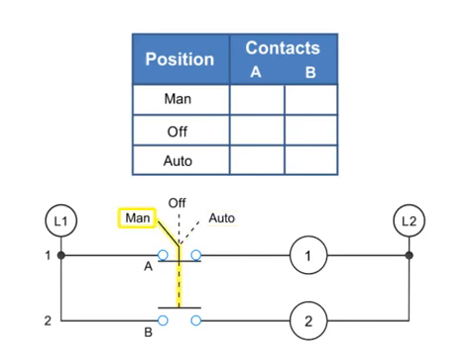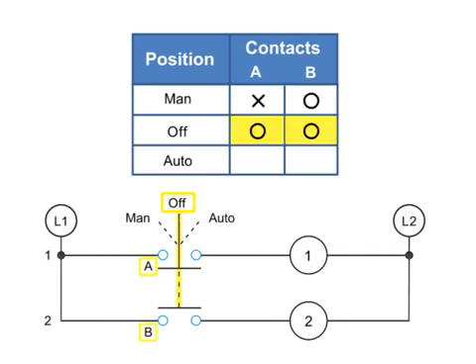Thus, in the MAN position, A is X, or closed, and B is O, or open. At the OFF position, both A and B are O, or open. With the selector switch set to AUTO, contact A is O, or open, and B is X, or closed.